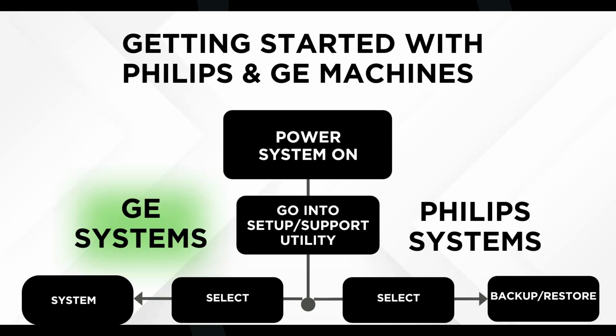All right. For GE systems, you would do user-defined configuration and service. Make sure you select your drop down from the media here, and then you would hit backup. Now for most GE systems, they're going to come up with a little warning, backup user-defined configurations, and it tells you where it's going to. You'd hit OK, and it should continue on with the backup. That one said user-defined. This one says here service, backing up the service settings folders.